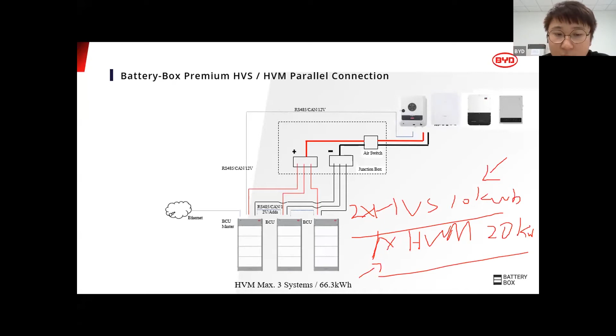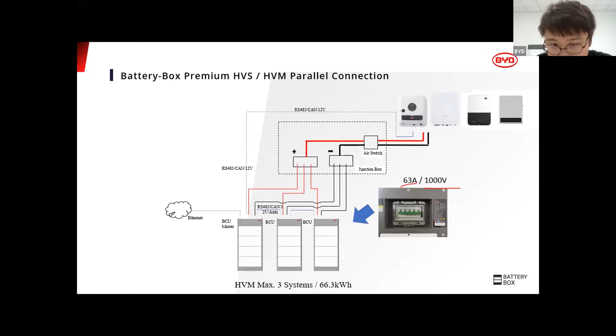One thing I want to mention here, and Leo is going to mention or show you exactly on the product itself: these high voltage batteries all come with built-in circuit breakers. It's a 63 amp, 1000 volts. We thought that this could be an easy story. You no longer need the external circuit breaker connecting to the inverters under the new Australian AS/NZS 5139 battery installation standard. But it turns out the 63 is way more than the inverter can handle.